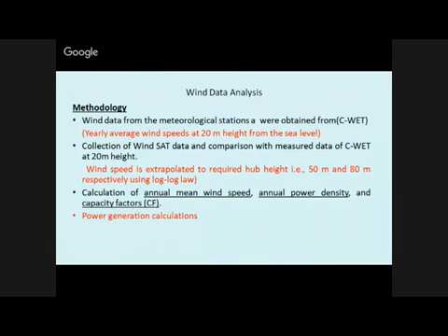So now the point is that data has been measured at 10-meter or 20-meter height, but we have to convert this velocity up to 80 meters or more, 100 meters or 120. In that case, a well-established log-log law is used, and using this law we can convert the velocity at 10-meter or 20-meter into the requisite height of 80 meters. I'll just show you that one.